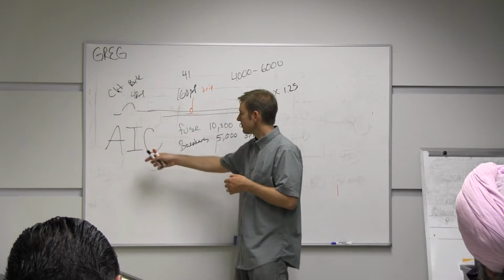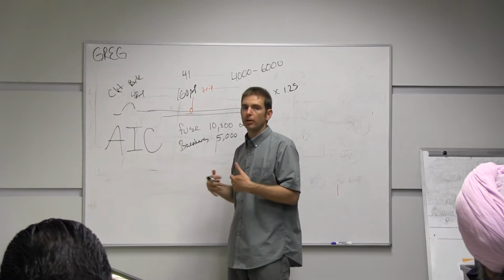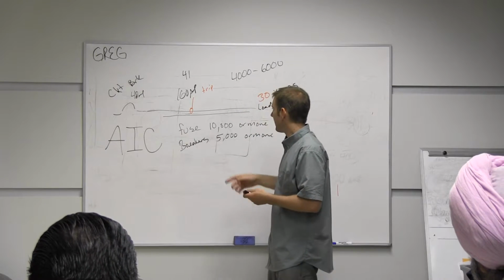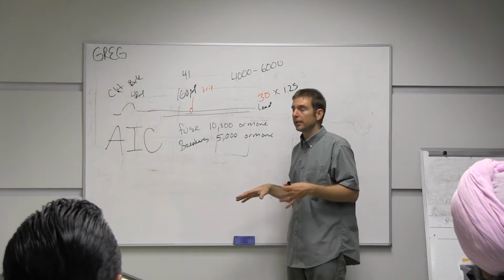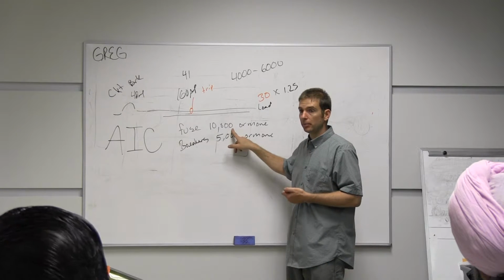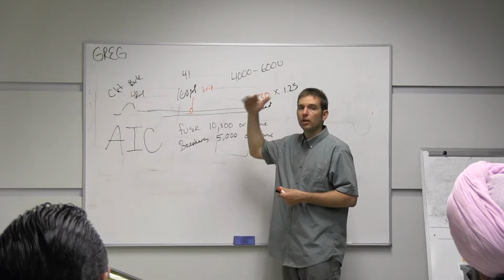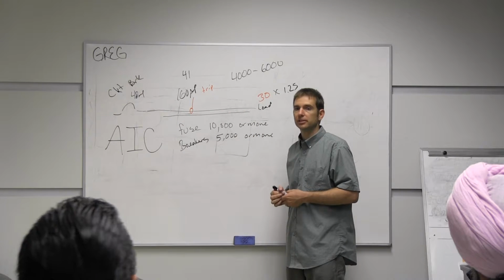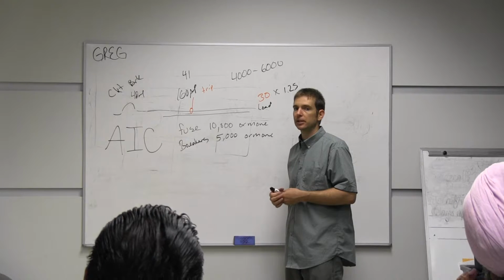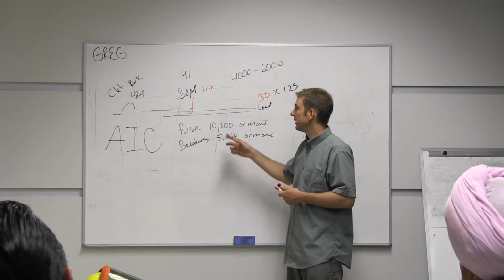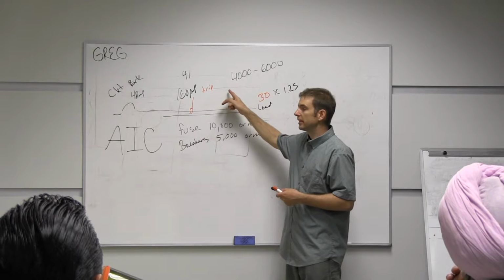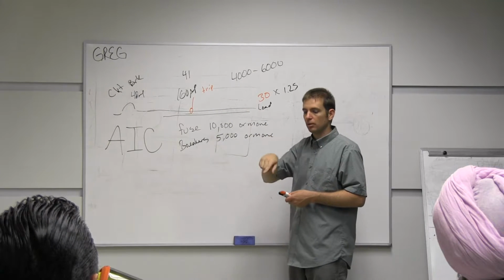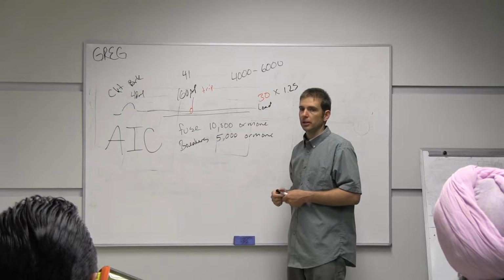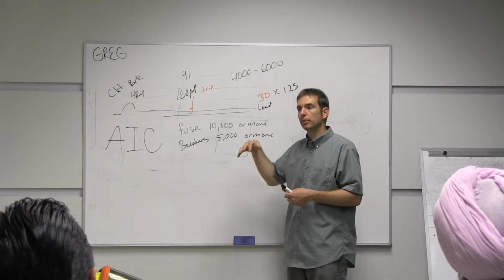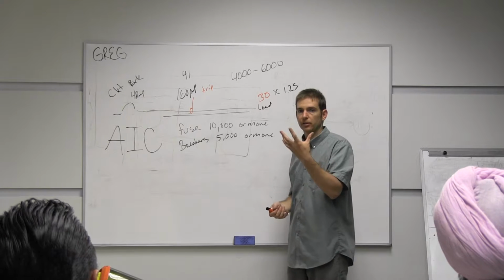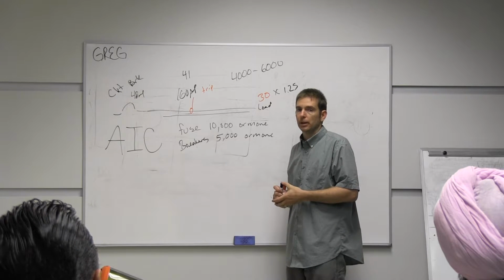So amps interrupting capacity. This is the available fault current also. So if I have at your facility, you don't have 10,000 AIC breakers, it's probably well above that. I would be surprised if you're not 65 or 100,000 amps interrupting capacity. So what does that mean? It means when you cut this wire, you could potentially have a bigger problem than just, oh, I damaged my wire strippers. Maybe you melted the tip off. Maybe you burned your hand. Maybe you put an arc flash in your face. Maybe the panel explodes. I don't know what's going to happen.